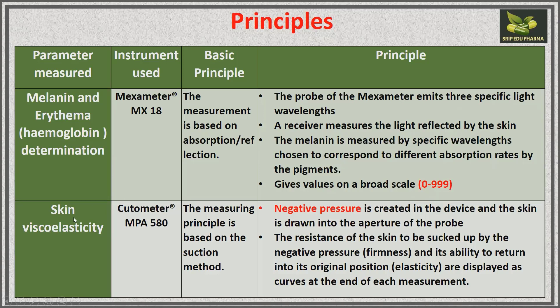For skin viscoelasticity, the instrument is the cutometer and the principle is the suction method — it sucks the skin so that viscoelasticity can be observed. Negative pressure is created in the device and the skin is drawn into the aperture of the probe. The resistance of the skin to being sucked up shows its firmness, and its ability to return to its original position shows its elasticity. Results are displayed as curves at the end of each measurement.